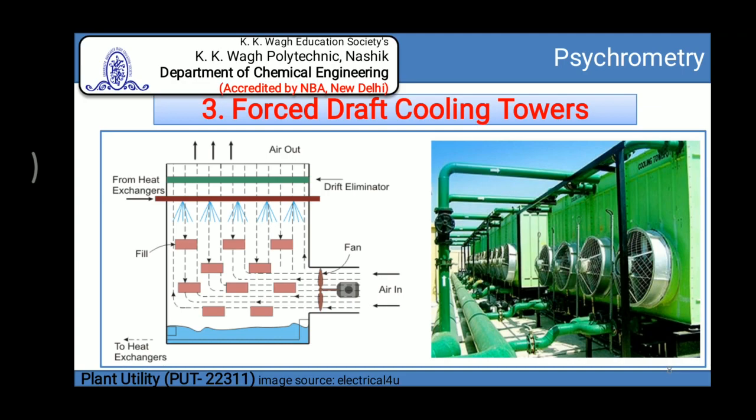The biggest disadvantage of the forced draft tower is that it may pick up the exit air from outside and push it back inside the cooling tower. This recirculation reduces the efficiency of the tower because the saturation level of inlet air increases.